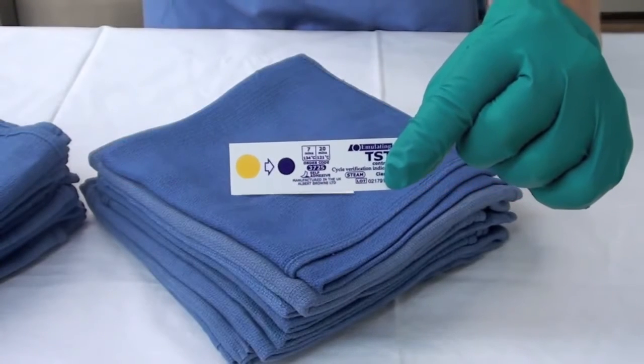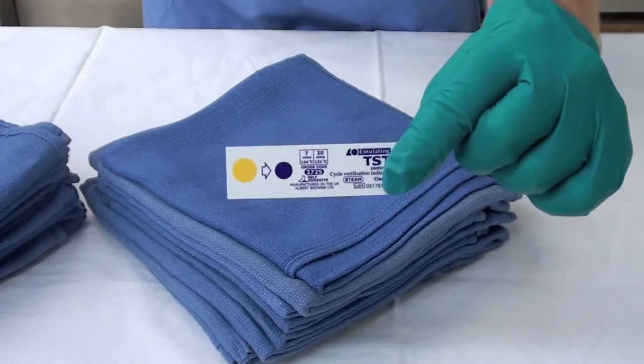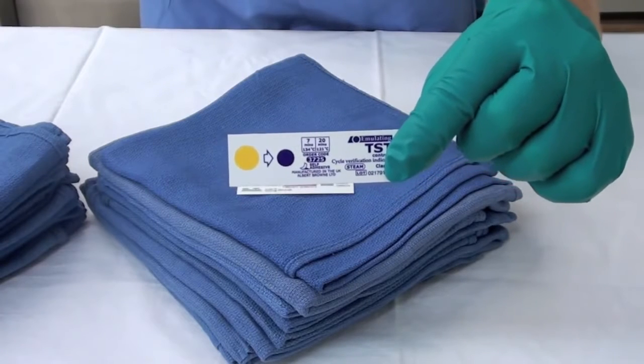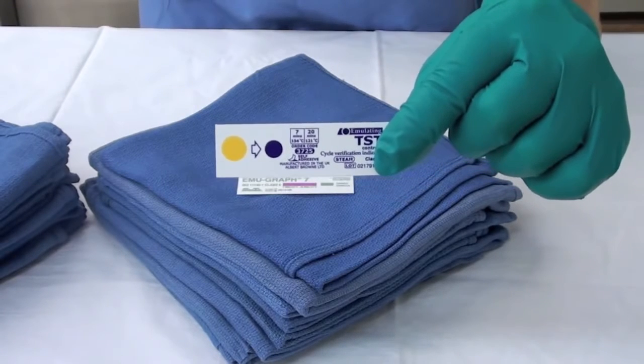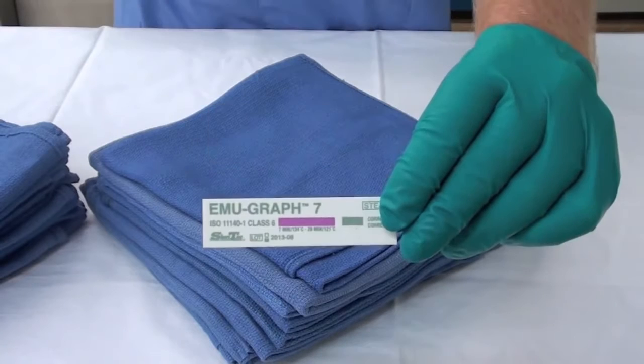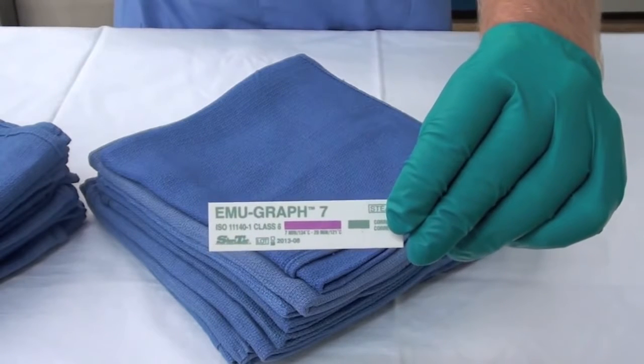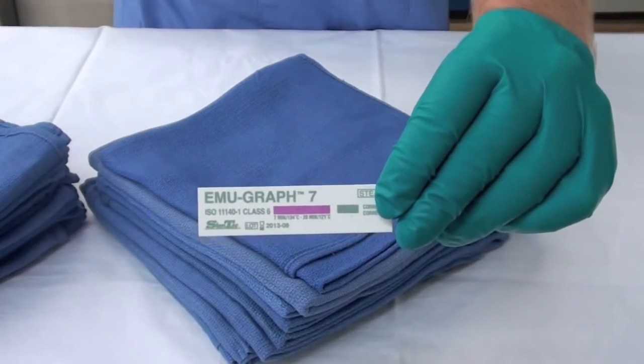This Steris Brown indicator is rated for 7 minutes at 134 degrees Celsius. In other words, this product claims that it will show a pass result once these conditions have been met. This SteriTech indicator is also rated for 7 minutes at 134 degrees Celsius.